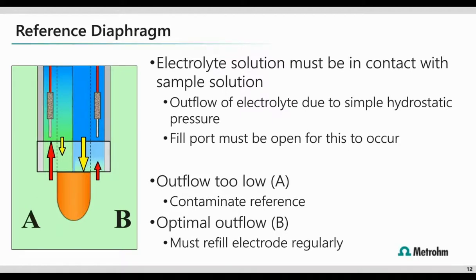So the only way this occurs is if that fill port is open. So write that down. During measurement, you must unplug the fill port at the top of the electrode. Remember, the measuring circuit we talked about earlier, if you don't open the fill port, you're not allowing that circuit to be completed by allowing that electrolyte to flow. So if we focus on the image on your screen, you'll see a couple scenarios to help us understand the importance of keeping the electrolyte solution topped off.